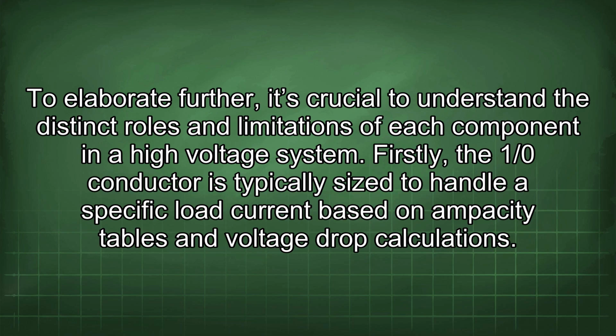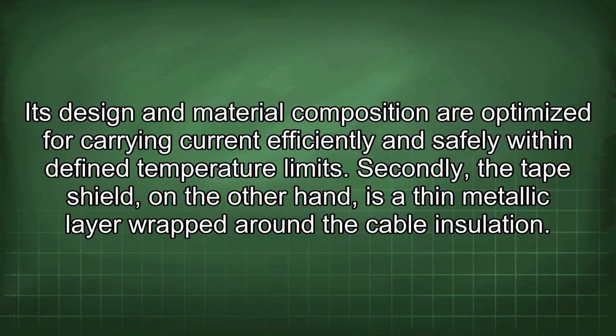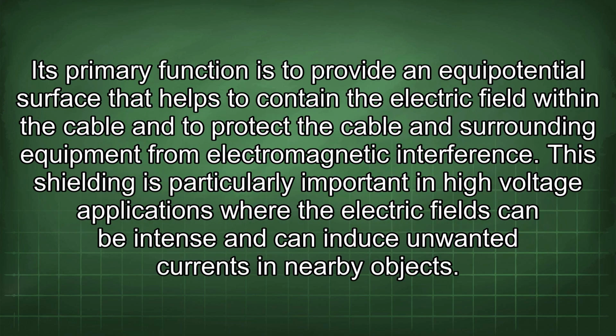Firstly, the 1/0 conductor is typically sized to handle a specific load current based on ampacity tables and voltage drop calculations. Its design and material composition are optimized for carrying current efficiently and safely within defined temperature limits. Secondly, the tape shield, on the other hand, is a thin metallic layer wrapped around the cable insulation. Its primary function is to provide an equipotential surface that helps to contain the electric field within the cable and to protect the cable and surrounding equipment from electromagnetic interference.